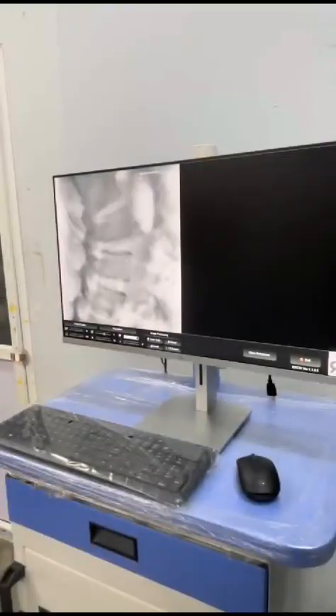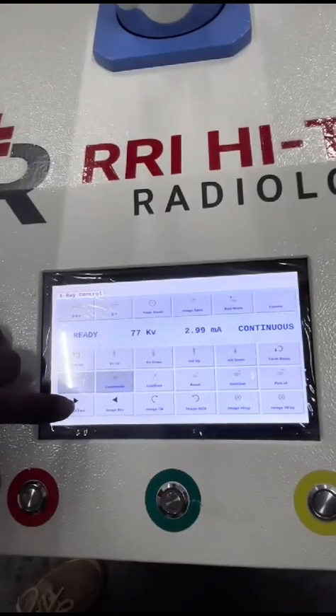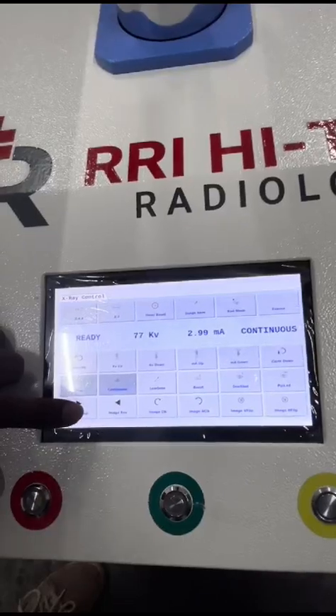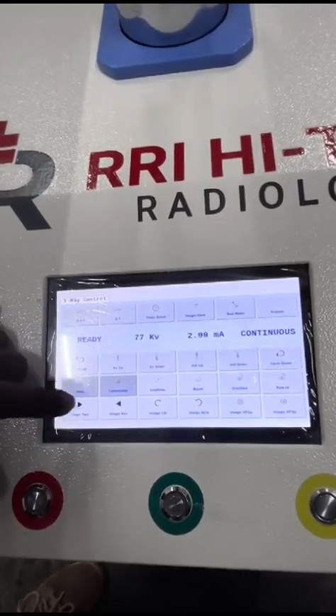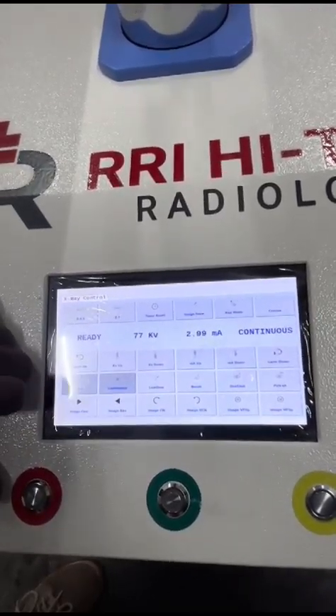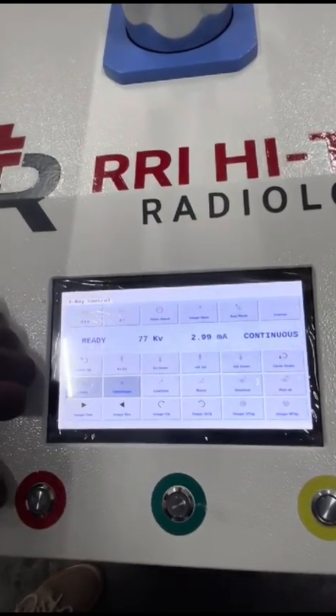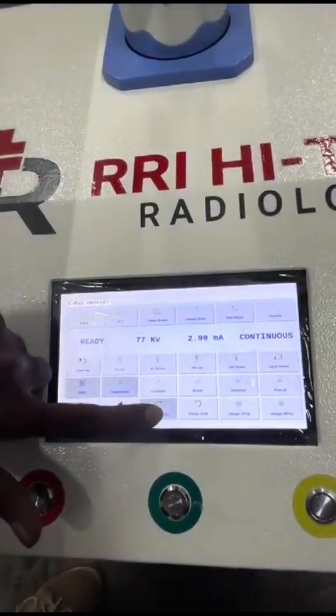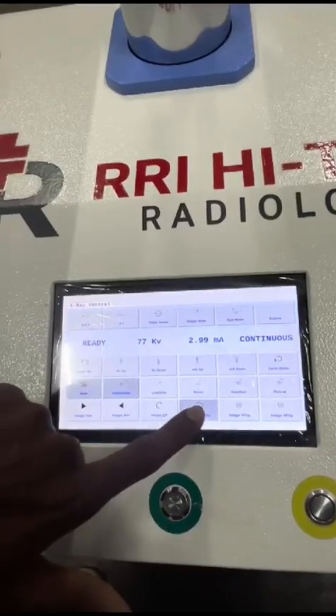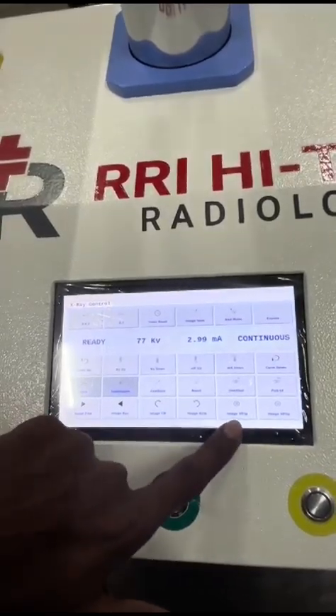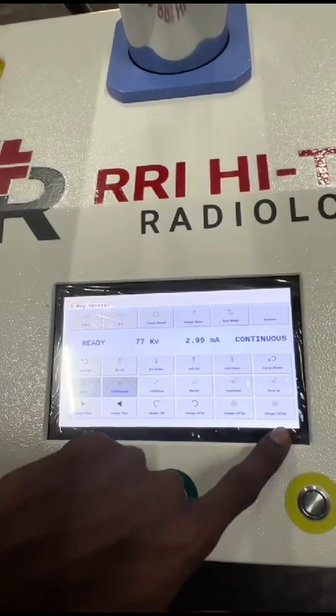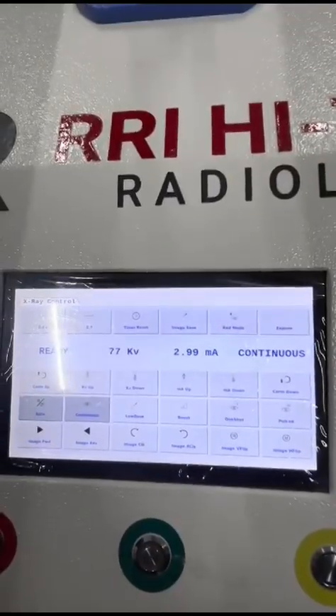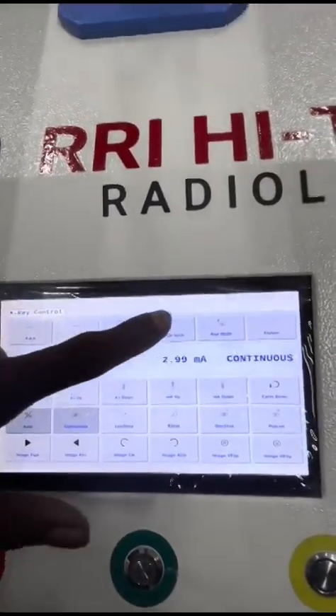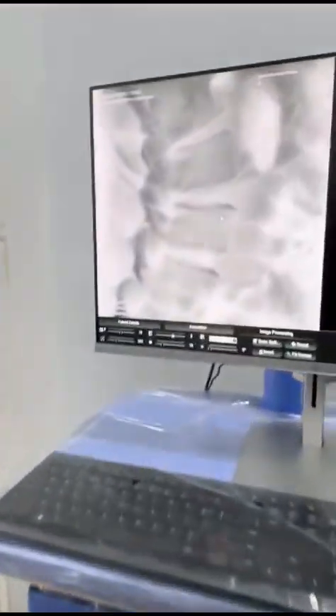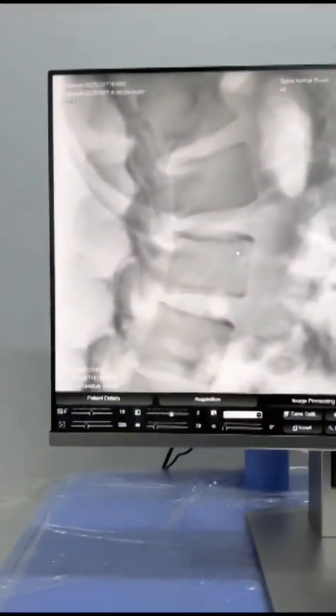You click the exposure and you get the image there. And in this menu we have image forward. We can change the images in the trolley, and we have image reverse, which will go to the old image. We have image clockwise. It rotates the image in a clockwise direction, and this one is for anti-clockwise direction. We also have image flip, vertical flip and horizontal flip, so you don't have to go to trolley to operate it. And also we have image save option. If you click image save, the image automatically saves in the trolley.